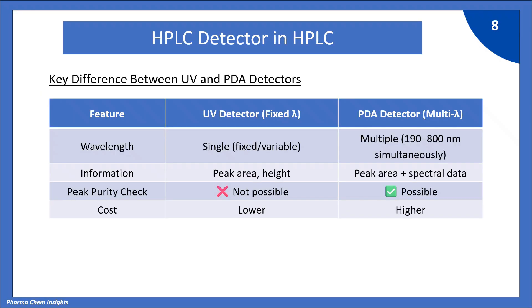Now let's see the key differences between UV and PDA detectors. First, wavelength: UV uses a single fixed wavelength, while PDA can simultaneously scan 190 to 800 nanometers. For information, UV provides peak area and height, while PDA provides peak area, height, plus spectral data. Peak purity check is not possible with a UV detector but is possible with a PDA detector. Finally, the cost of a UV detector is lower while a PDA detector costs more.